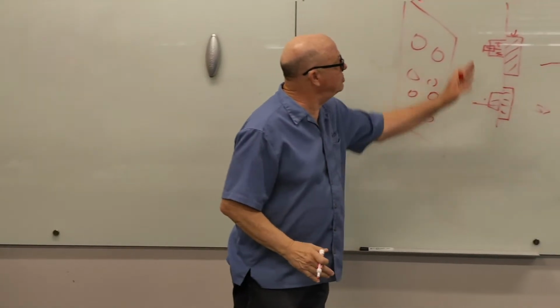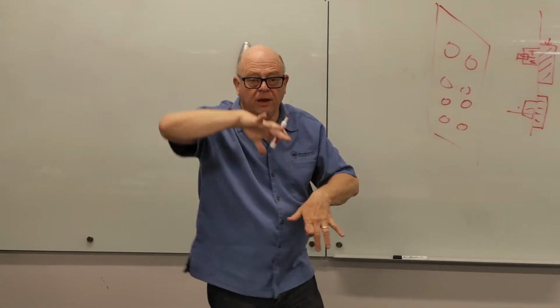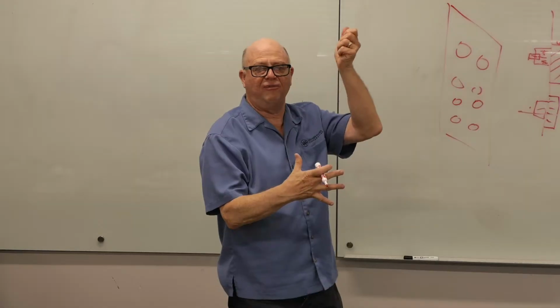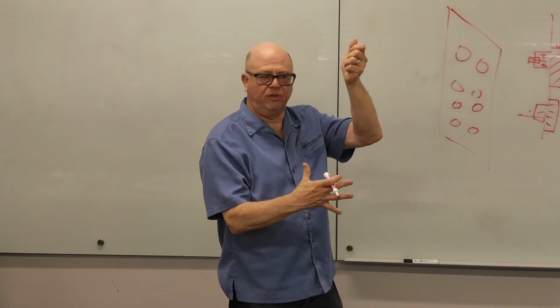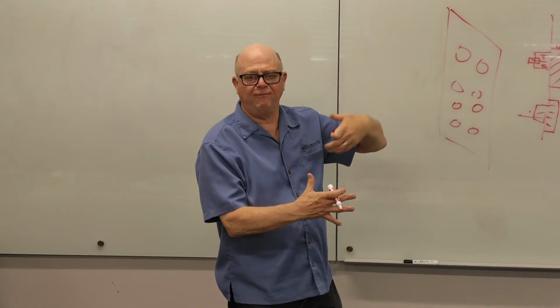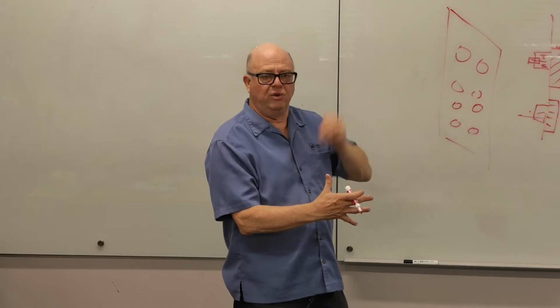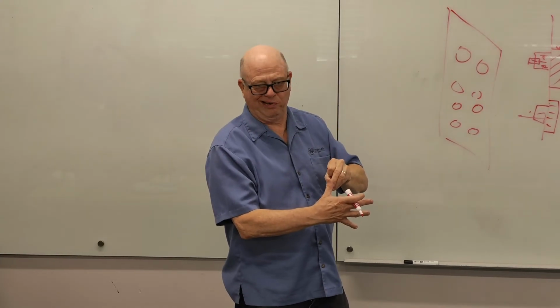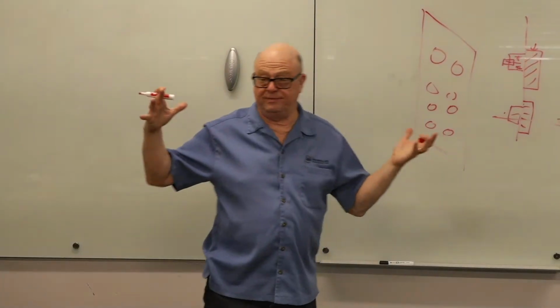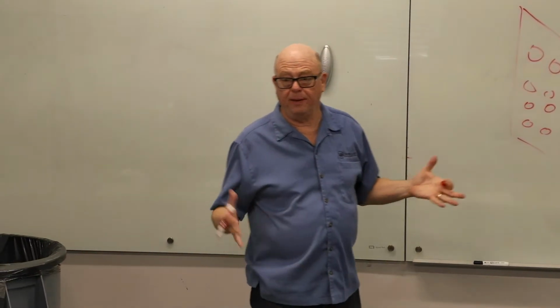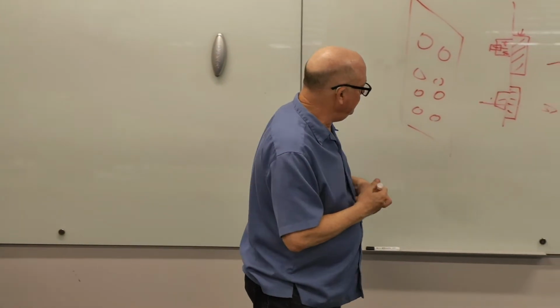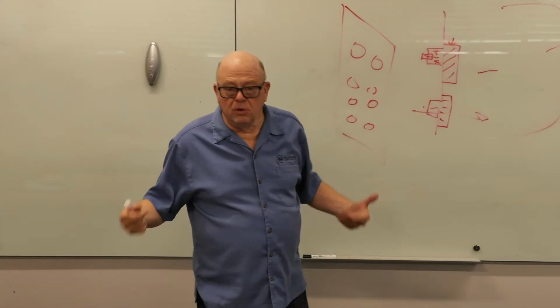motorized and controlled in a sequence that when you take them offline, first you shut it, then you turn off the motor, and then you sit there until at some point later you need that fan to run. You start the fan, you get it up and going the correct direction, and then you open the damper. Okay? This was a hard-learned lesson.